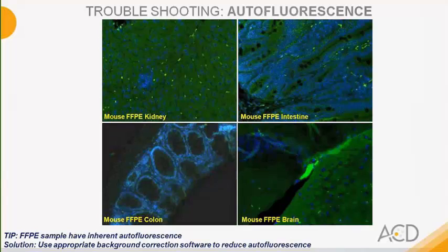Another topic I want to cover here is autofluorescence. So here are some examples of autofluorescence in various FFPE samples. The green dots you see here are not real RNAscope signal, and it's all attributed to tissue autofluorescence. So one tip to keep in mind: FFPE samples always have inherent autofluorescence. So it's very likely you're going to run into this autofluorescence issue if you work with FFPE samples using a multiplex fluorescent assay. So the solution is to use appropriate background correction software to reduce autofluorescence.